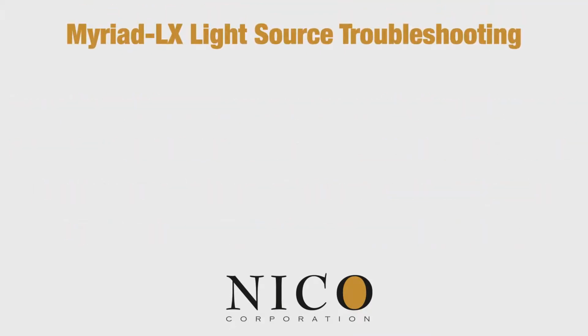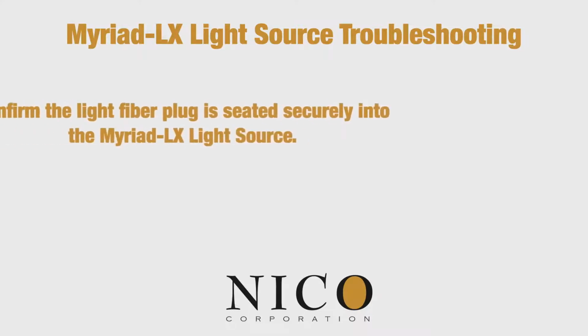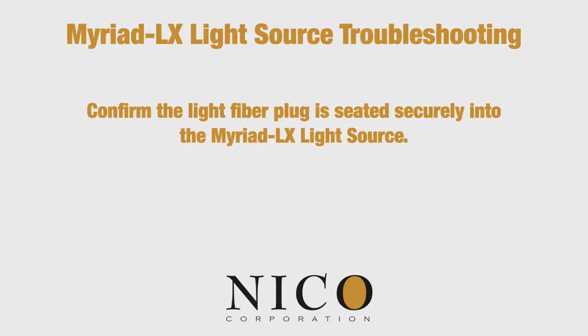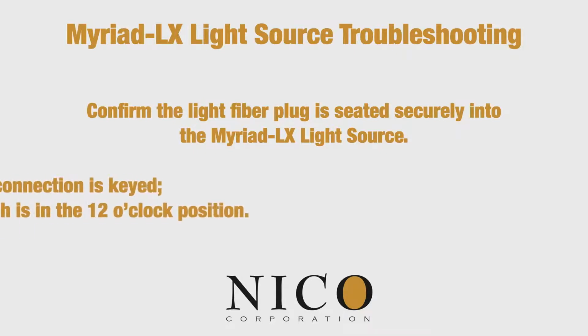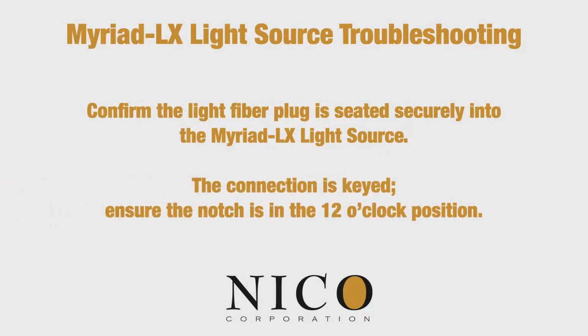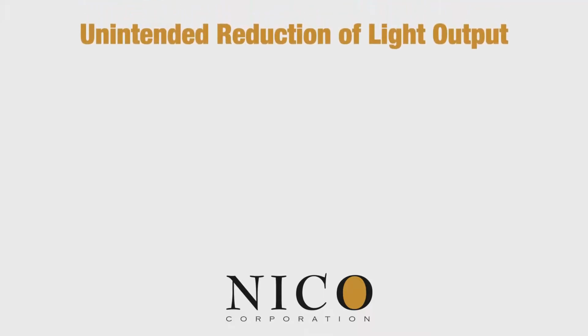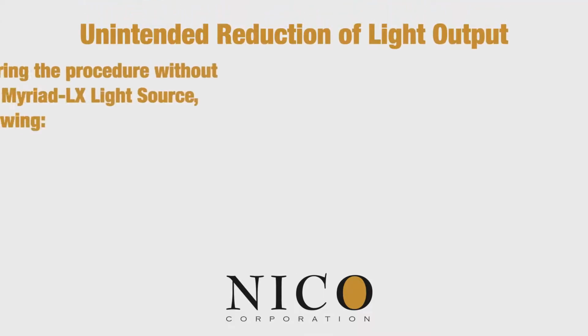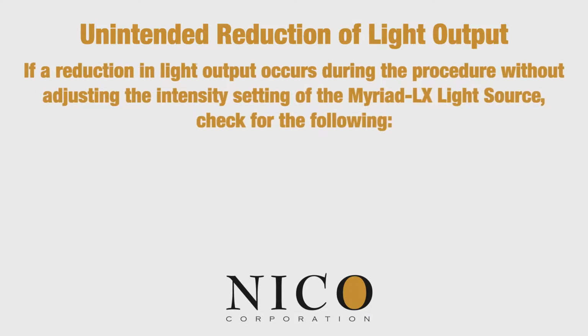Myriad-LX light source troubleshooting. Confirm the light fiber plug is seated securely into the Myriad-LX light source. The connection is keyed. Ensure the notch is in the 12 o'clock position. Unintended reduction of light output.